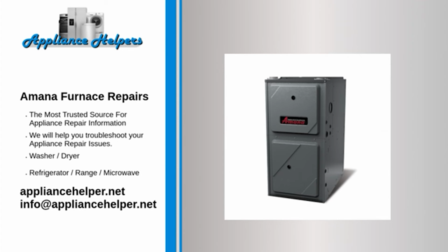Amana furnace starts then stops. The flame sensor monitors the burner to detect whether or not a flame is present. If the flame sensor is defective, it might fail to detect a flame. If the flame sensor does not detect a flame, the control board will shut off voltage to the gas valve to prevent the furnace from heating. Sometimes, if the flame sensor is dirty, it will fail to detect a flame. Try cleaning the flame sensor with a fine abrasive pad. If the furnace still doesn't heat, replace the flame sensor.